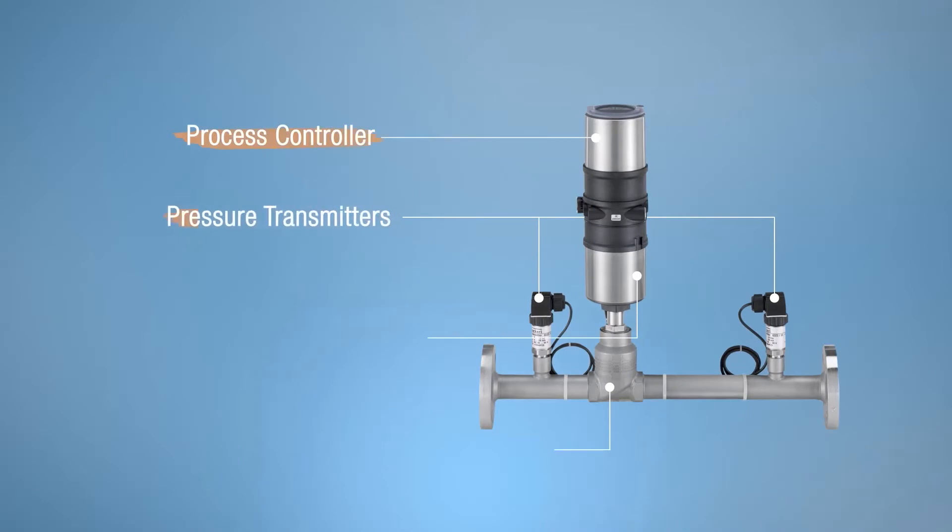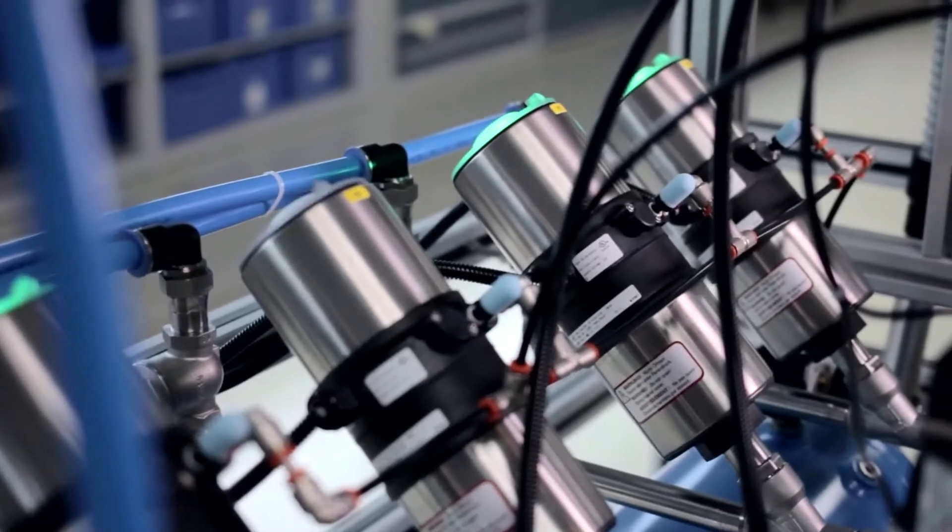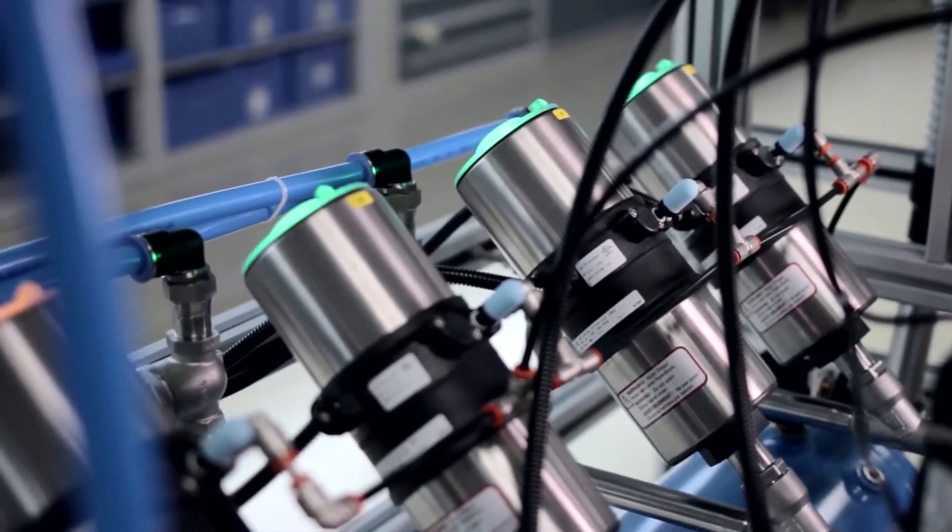The two pressure transmitters feed back the pressures before and behind the valve orifice to the controller. The controller can calculate the flow value and then if the flow value deviates from the set point, the type 8750 controller adjusts the valve automatically in order to reach the set point.